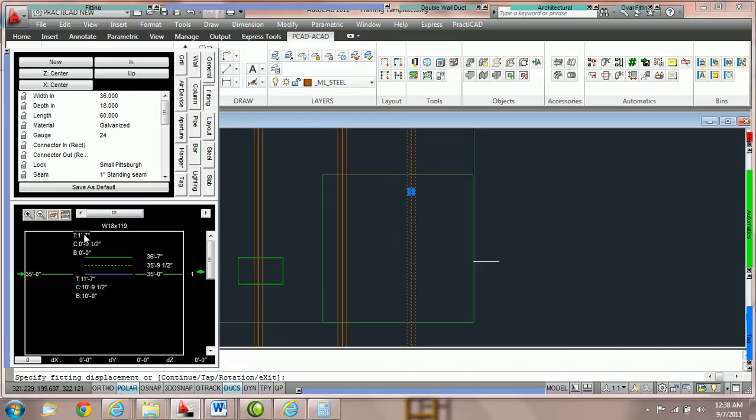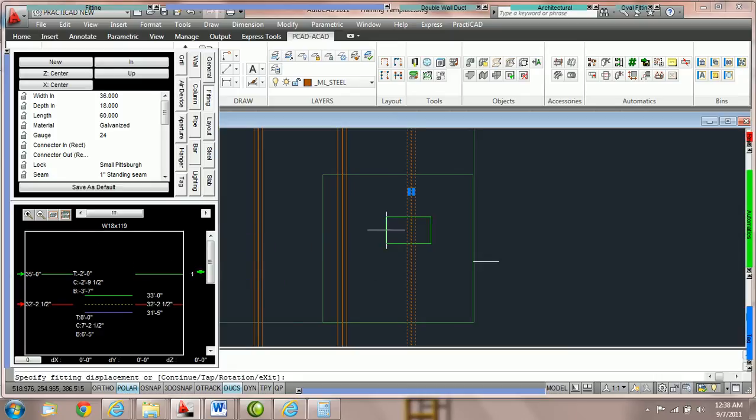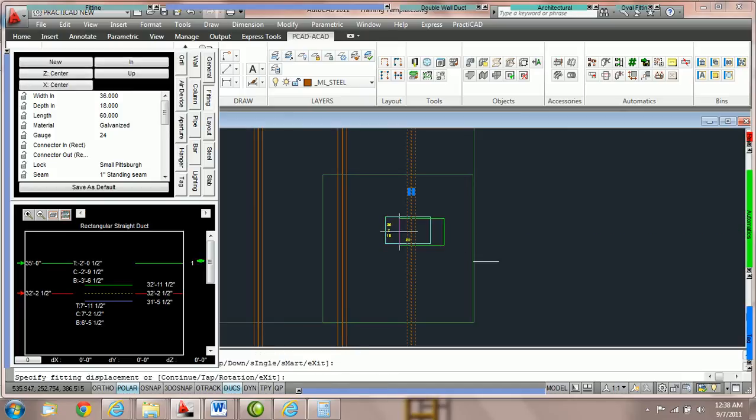So for example, if I wanted to make the top of duct 2 feet underneath relative top, we can click here and type in -2 foot. That would mean the top of duct is 2 feet underneath our steel beam. And we're going to place it right here. And if in fact we wanted bottom of duct to be 5 foot above the slab, I could say bottom of duct 5 foot. So generally we use the top as a reference point from relative top, and we use the bottom here as a reference point from relative bottom. These are usually the two values we focus on.